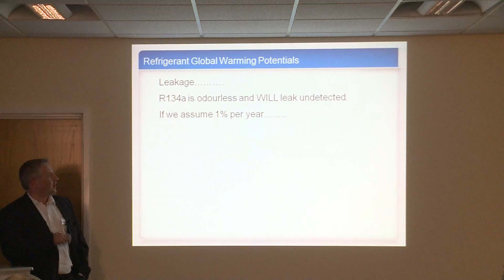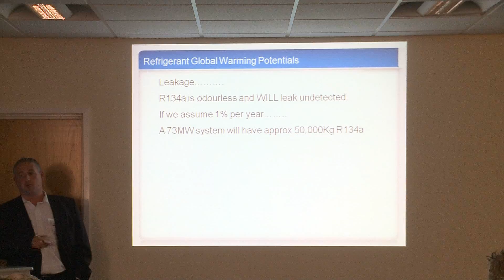A large plant we looked at - and this is a concern of mine as we see more people interested in district heating and heat pumps for district heating - is that we forget about the global warming potential if these plants are using HFCs. A 73 megawatt system we were looking at in South Korea would have about 50,000 kilos of R134A in it, leaking about 500 kilos per year.